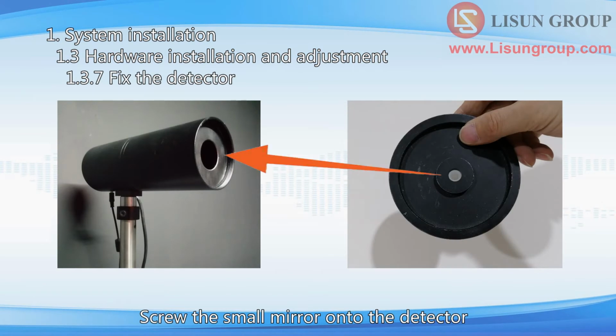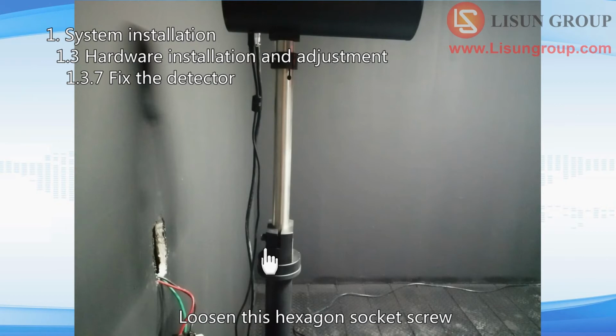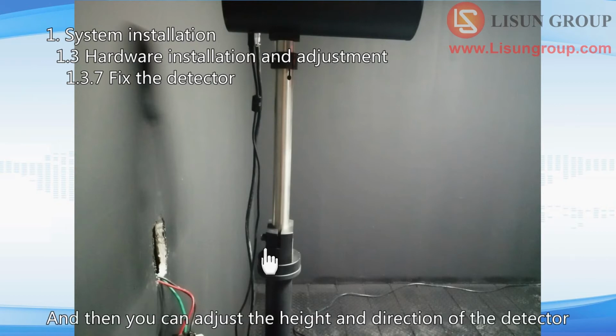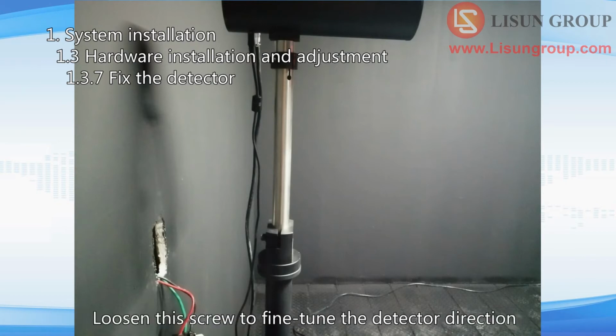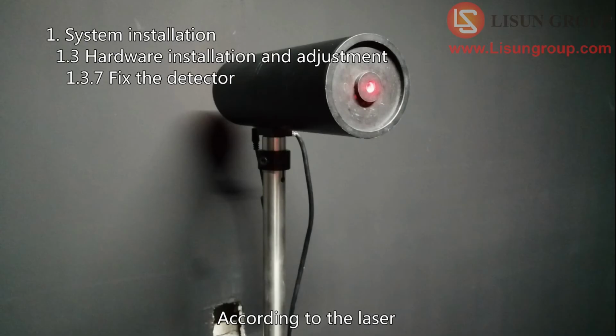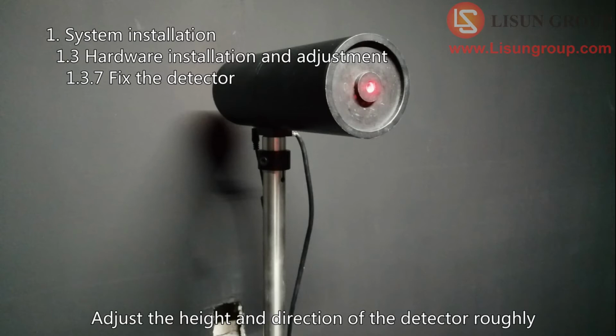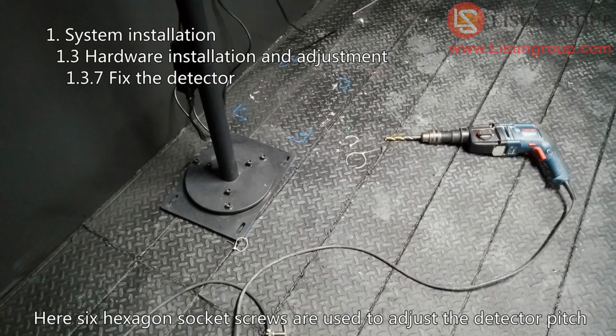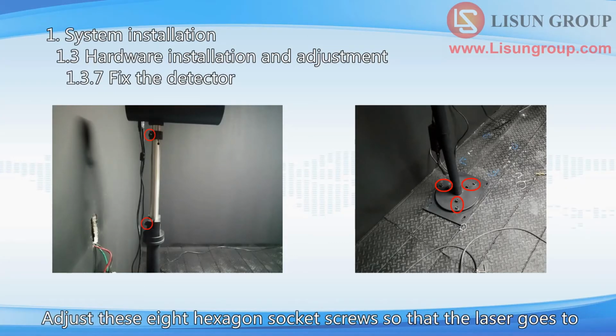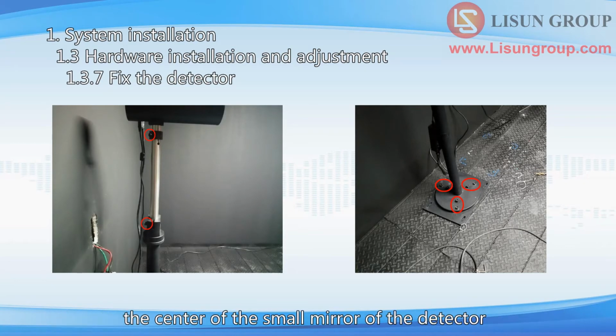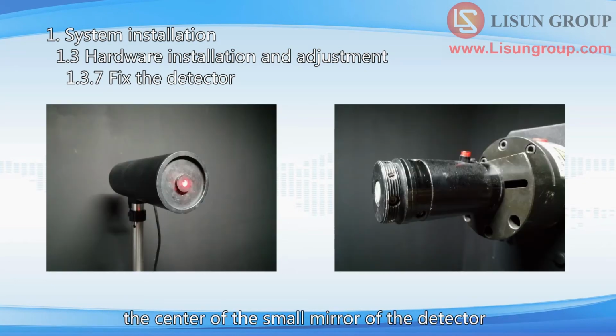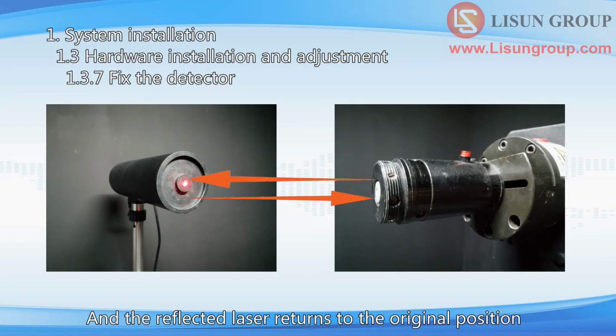Screw the small mirror onto the detector. Loosen this hexagon socket screw, and then you can adjust the height and direction of the detector. Loosen this screw to fine-tune the detector direction. According to the laser, adjust the height and direction of the detector roughly. Here 6 hexagon socket screws are used to adjust the detector pitch. Adjust these 6 hexagon socket screws so that the laser goes to the center of the small mirror of the detector, and the reflected laser returns to the original position.